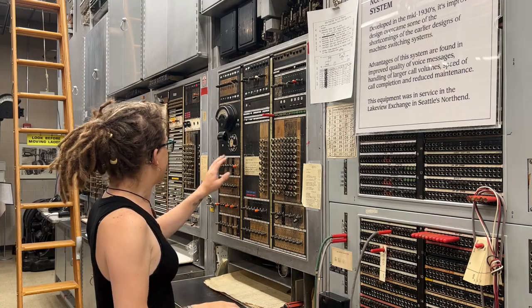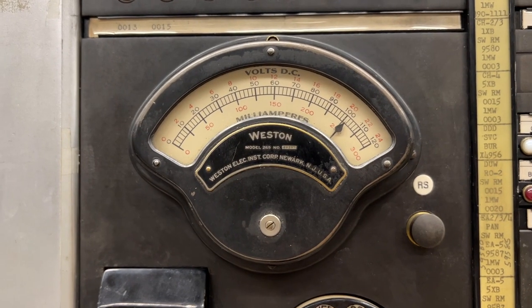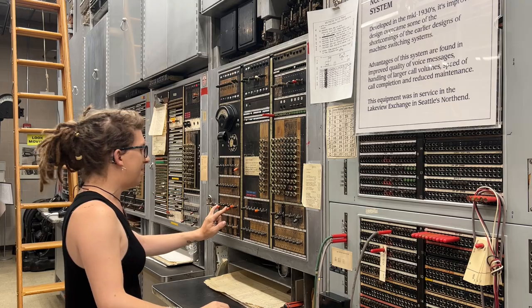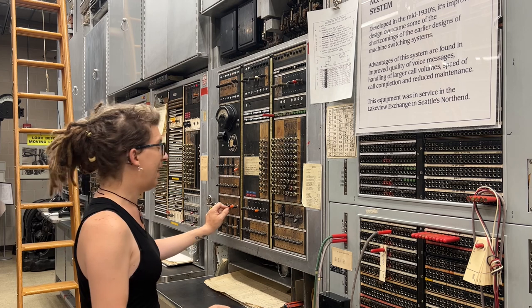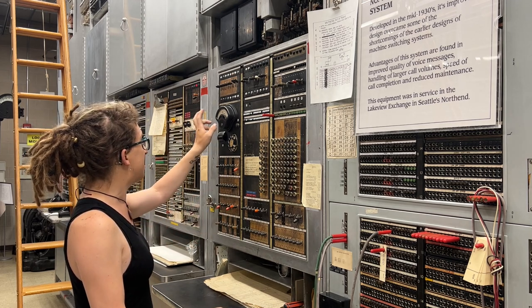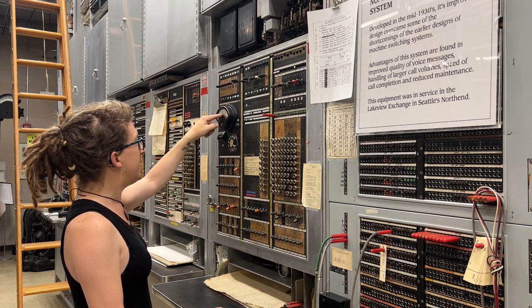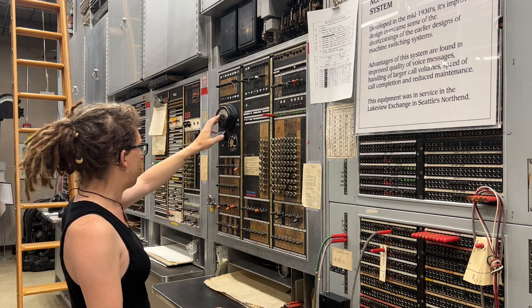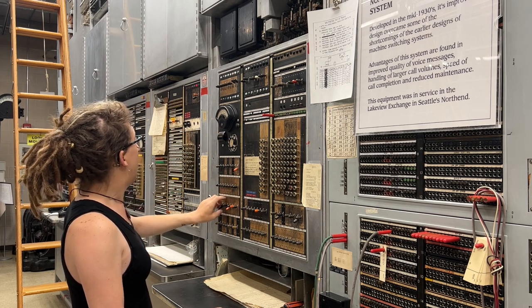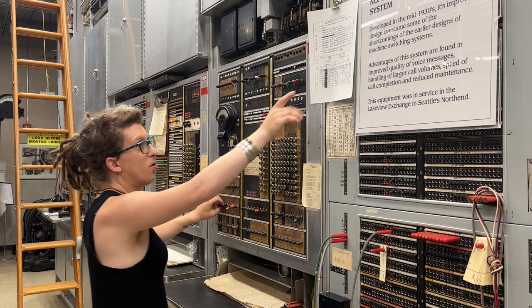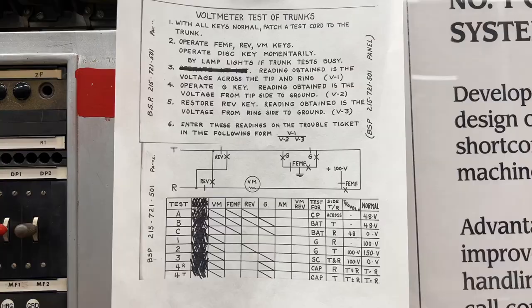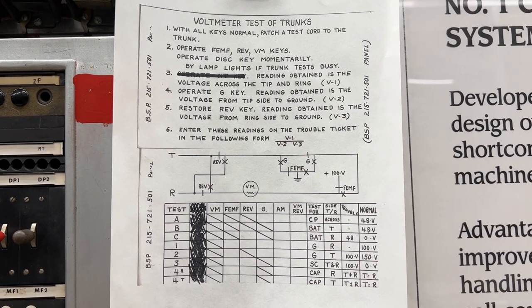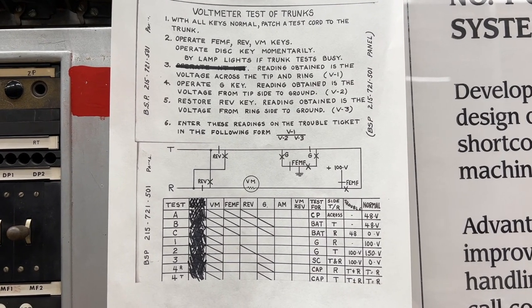The first thing I can do is throw a voltmeter on it. The voltmeter circuit is actually pretty clever — it will tell me all sorts of things about the electrical health of that trunk. The most straightforward thing is to see whether I'm getting the proper voltage of the proper polarity coming back from that trunk, and I am. There's a whole circuit for the voltmeter where you can do all sorts of things, and it shows you for each test what you're testing for, what is a good result, and what is a bad result.